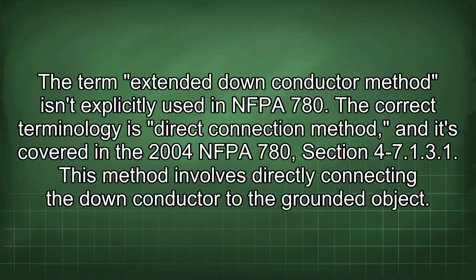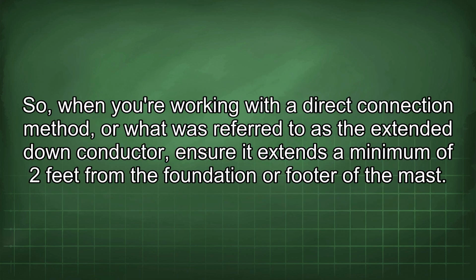The term extended down conductor method isn't explicitly used in NFPA 780. The correct terminology is direct connection method, and it's covered in the 2004 NFPA 780 section 4-7.1.3.1. This method involves directly connecting the down conductor to the grounded object. So, when you're working with a direct connection method, or what was referred to as the extended down conductor, ensure it extends a minimum of 2 feet from the foundation or footer of the mast.